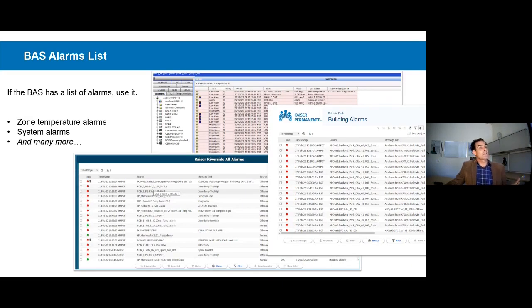If we're not connected to Clockworks, then we can still get a list of faults. You have to get it from the BAS system. Every BAS system since the inception of BAS system has a list of alarms in it. So these are the alarms that our engineers get every day. So simply gathering a couple weeks or a month's worth of these alarms lists will give us an inventory of where those problems are happening.